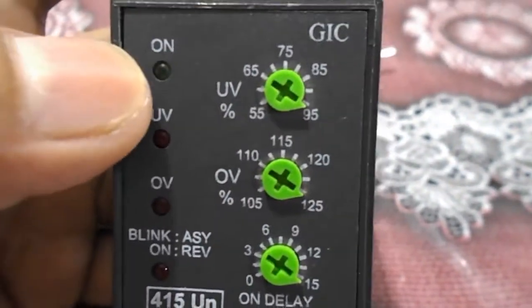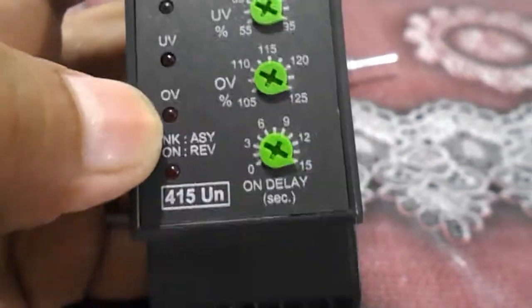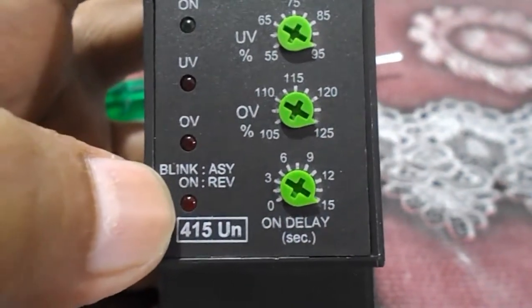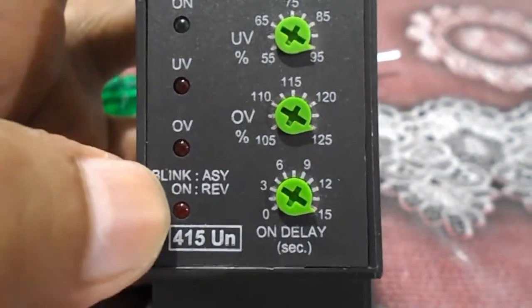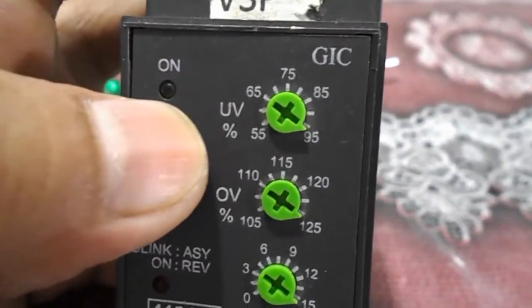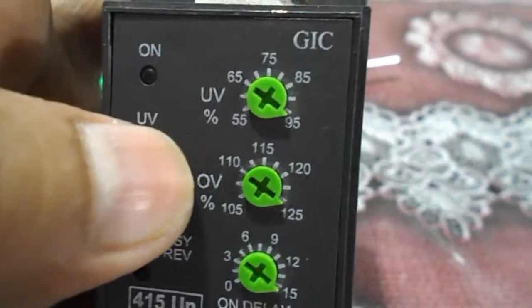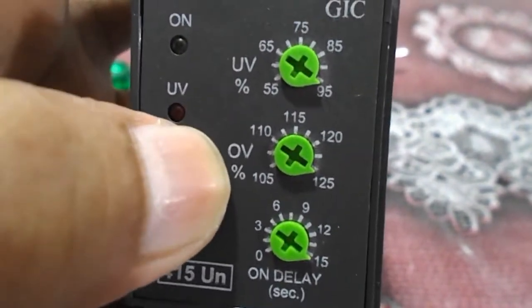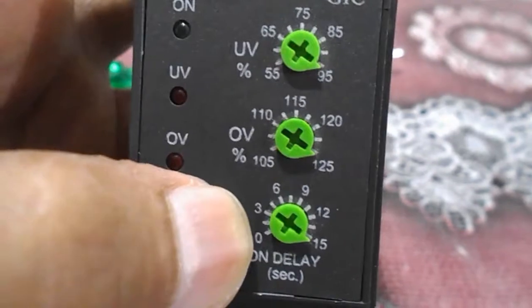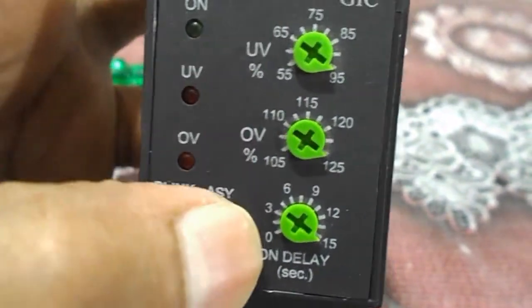On this three phase preventer there are indicator lights: ON indication, under voltage, over voltage, and a blink indicator for reverse phase. There is a button where you can set the under voltage percentage — at what percentage you get an under voltage fault, at what percentage you get an over voltage fault, and at what time delay the fault will appear.